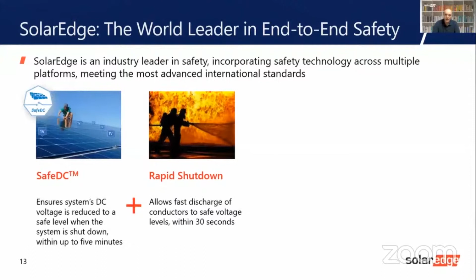We also have rapid shutdown component capability built into the SolarEdge solution. So this is a mandated requirement today, of course, in many regions, and you'll hear later from my colleague about the forthcoming rapid shutdown requirements for the Thai market. But this capability allows the fast discharge of conductors to a safe voltage within 30 seconds, which is the normal mandated regulation requirement. In addition, we have arc fault interruption.